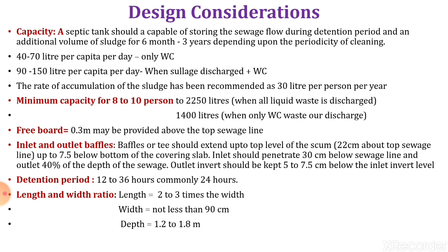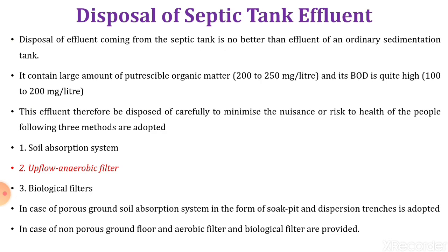Length and width ratio. The length should be 2 to 3 times the width. Width should not be less than 90 centimeter. Depth should be between 1.2 to 1.8 meter. Then the disposal of septic tank effluent.